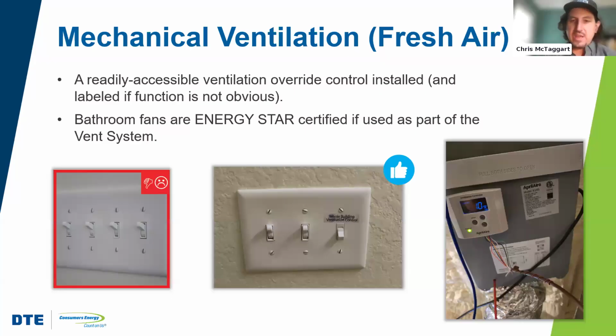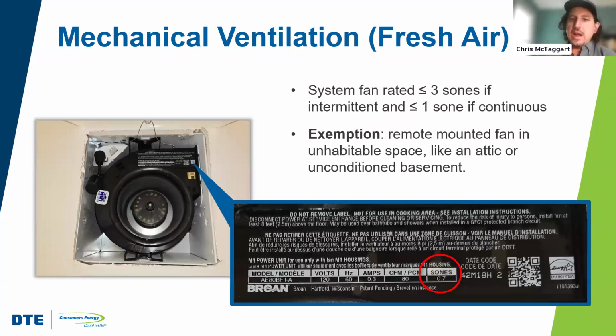Other things: you have to label the system controls, and there has to be an override. And why is that? Well, imagine you're on a day where it's really foul air. We get one of those Canadian wildfire smoke days. You want people to be able to turn it off if it would really be better ultimately. So again, if you're going to use exhaust only and you're going to use Energy Star bath fans, then you have to use Energy Star bath fans.